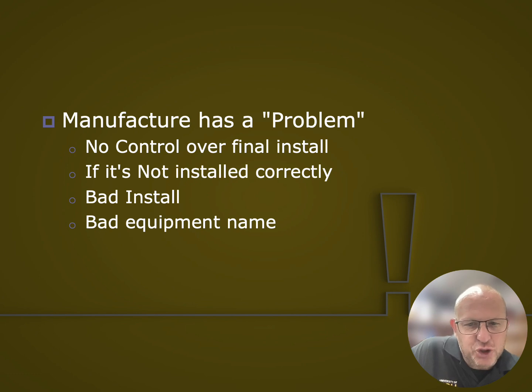So manufacturers have an issue, and that issue is with the installers. They have no control over who is installing their piece of equipment. So the final installation comes down to individuals who have been trained, maybe not by the factories themselves, but possibly by other technicians that are in the field. I'm currently on a series called They Can Learn That in the Field, and different ways that technicians are learning the wrong ways to install AC systems in the field, such as only pulling 30-minute vacuums and not going over the checklist that the manufacturer gives us.